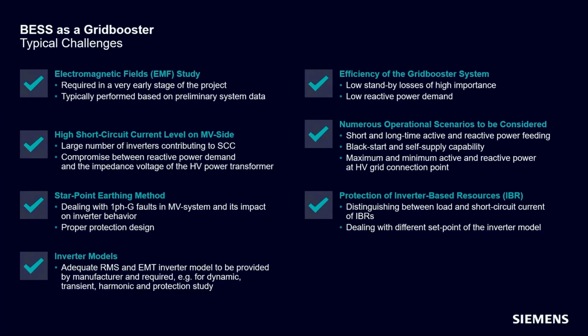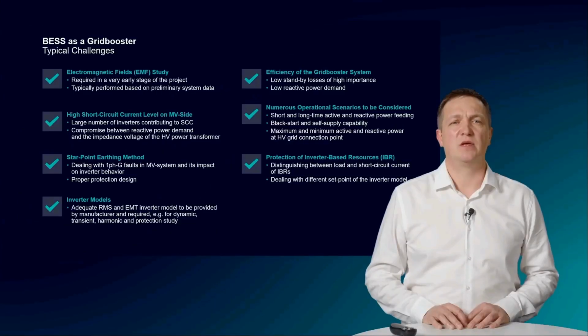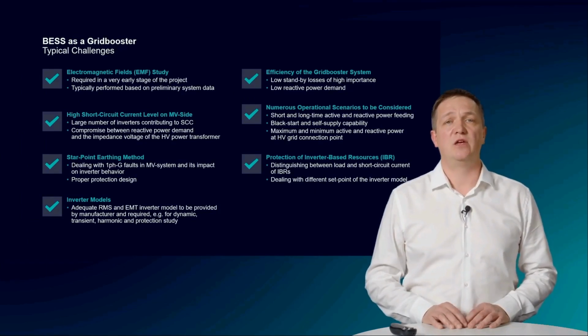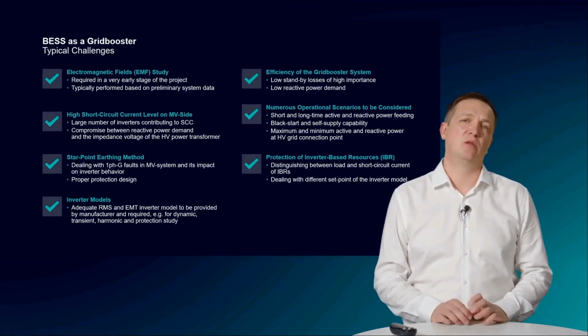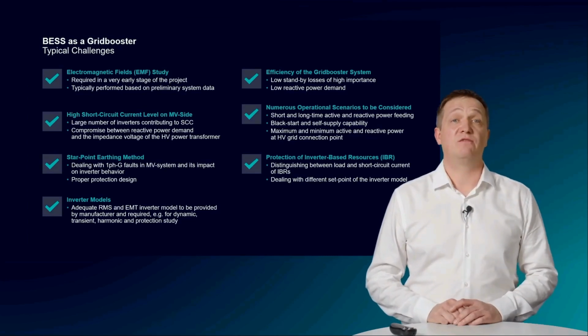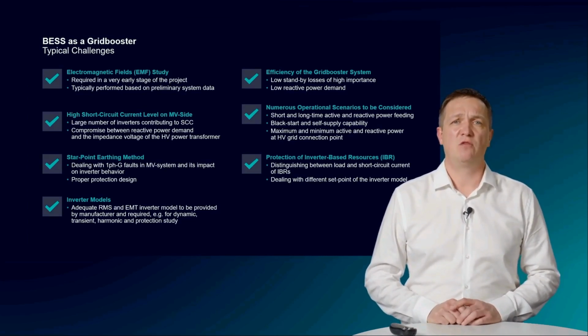But there could be some limitation achieved by increasing the impedance of the high voltage transformer. Unfortunately, by increasing the impedance, mainly the reactance of the transformer, the reactive power demand of the grid booster increases as well, so that sometimes a compromise needs to be made between the switchgear design, the inverter rating, and possible operational modes. This is a very time-consuming and extensive process involving different teams from the design and manufacturer side.